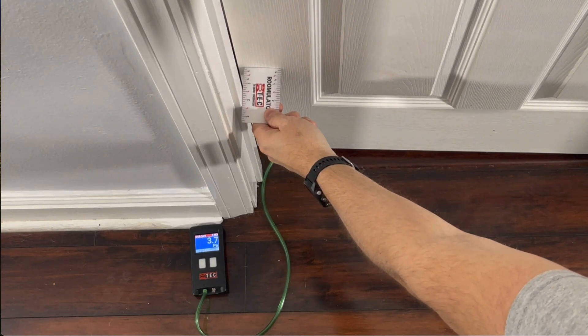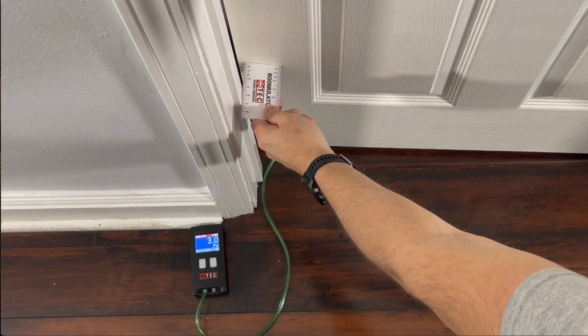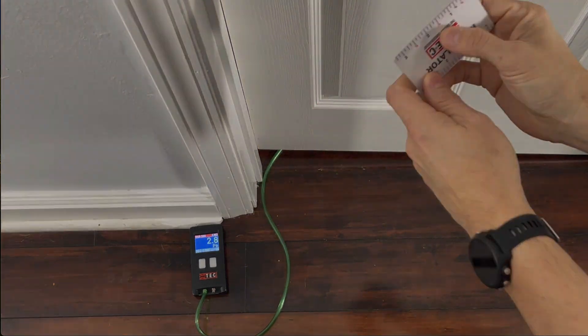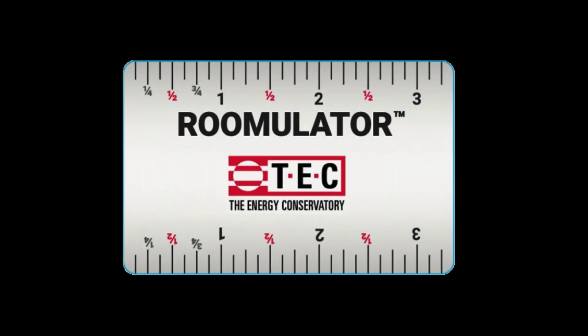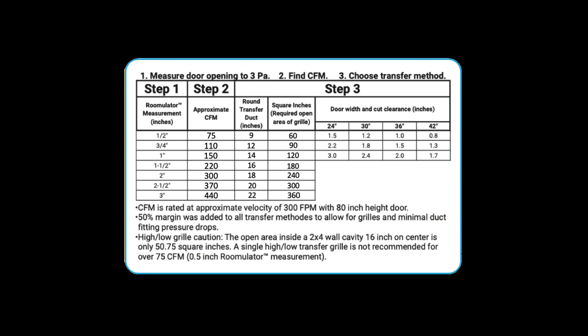Open the door until the gauge reads 3 pascals, then record the measurement on the roomulator. As we flip the card over, let's follow the process from left to right. We can see that we have just completed Step 1 — measuring our door opening to 3 pascals, with an opening of one and a half inches.